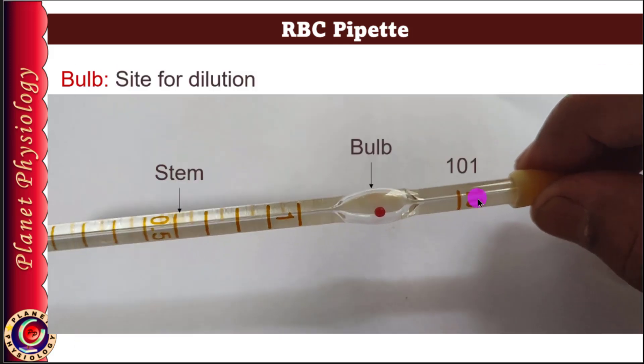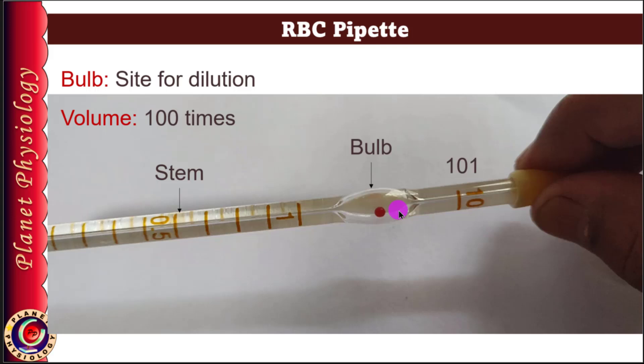Now let's take a closer look at the bulb. The lumen of the stem expands to form the bulb. It is thin-walled and narrows down on the other end to form a thick and short part similar to the stem. The bulb is the place where the blood sample is diluted. In the case of the RBC pipette, the volume of the bulb is 100 times that of the stem. This is evident from the numbers mentioned on the pipette: the marking at the beginning of the bulb is 1 and at the end of the bulb is 101, indicating the bulb holds 100 times the stem volume.